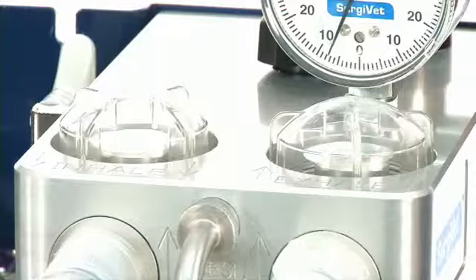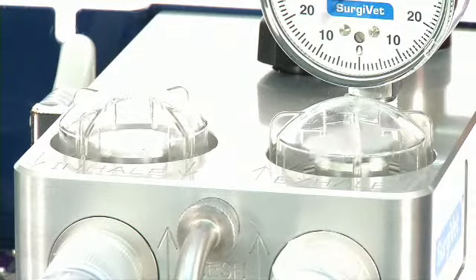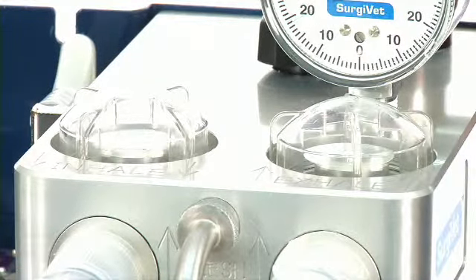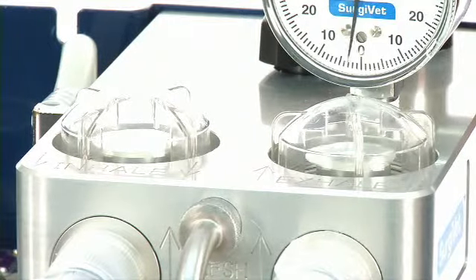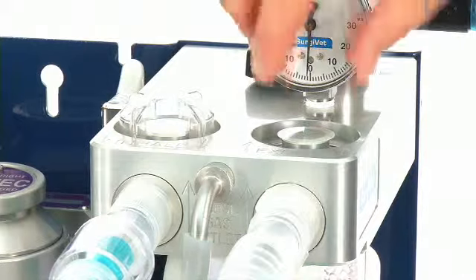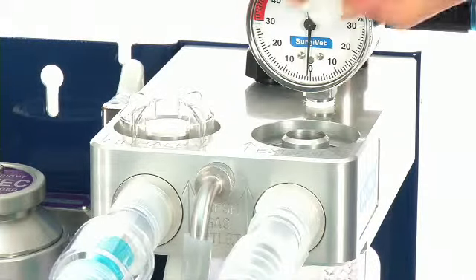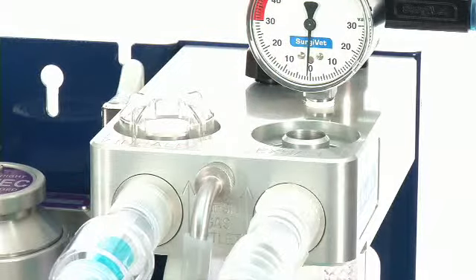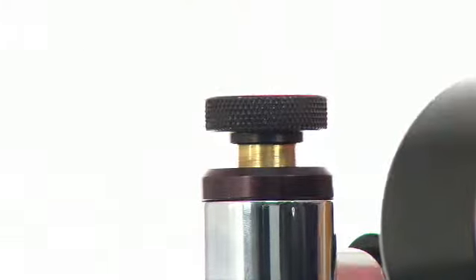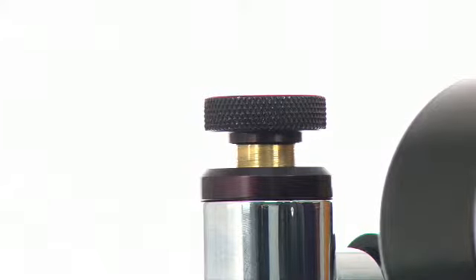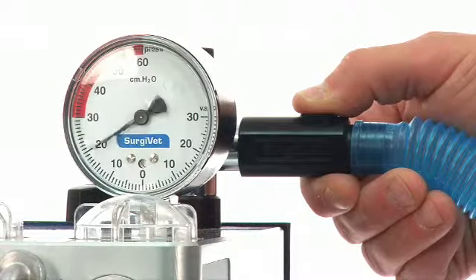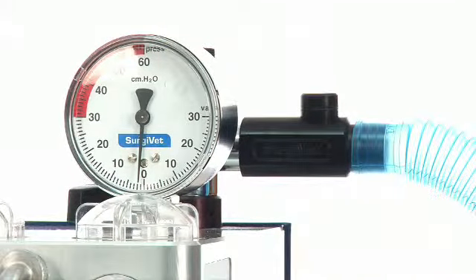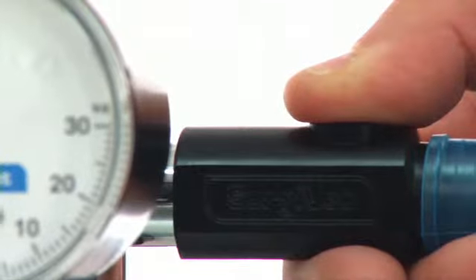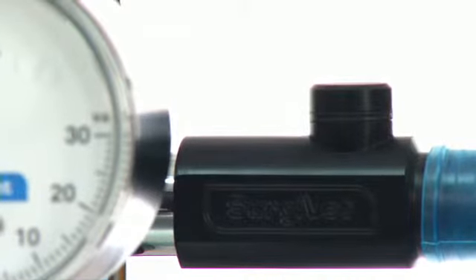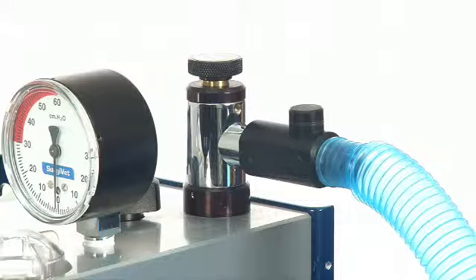The flutter discs in the inhalation and exhalation dome caps should be inspected weekly for any visual damage, warping, or discoloration. If any of these are observed, they should be replaced. Clean with a mild soapy water solution, rinse, and dry completely. Inspect the pop-off valve daily to ensure that it completely opens and closes smoothly with no problems. Inspect the pop-off occlusion valve daily, if available, on the anesthesia machine. Ensure that the spring-loaded button moves up and down smoothly. If there is any resistance or questionable function, remove it from use and replace if necessary.